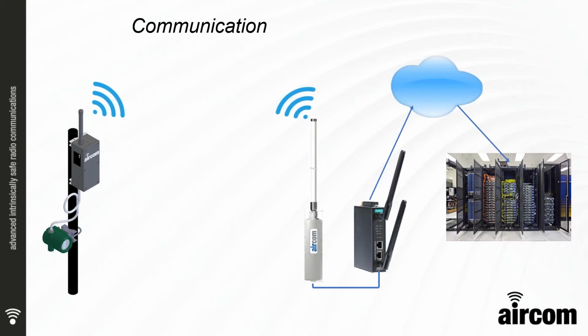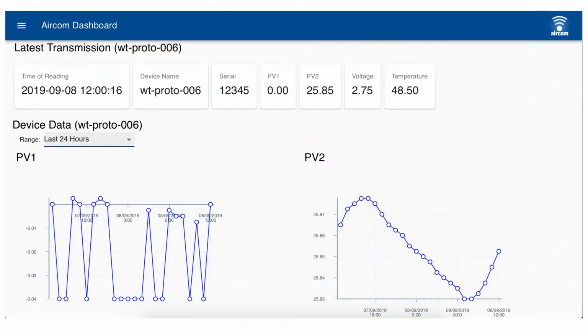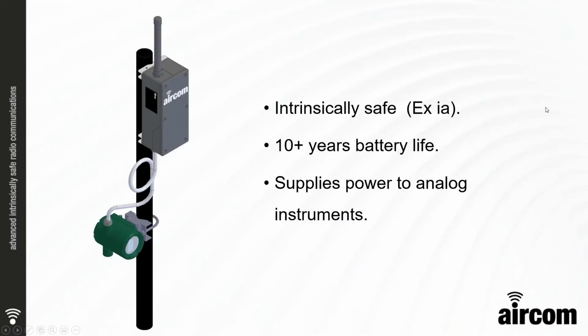This connection can equally be made to a physical server, or we can provide a Modbus output to go direct into a SCADA system, a PLC, or a DCS. Once the data is collated, the user can utilize various different HMIs to display the data and perform any functions and controls they may need to with that instrumentation data. The AIRCOM device is intrinsically safe, Ex ia. It has potentially 10+ years of battery life, and it powers the analog instruments.